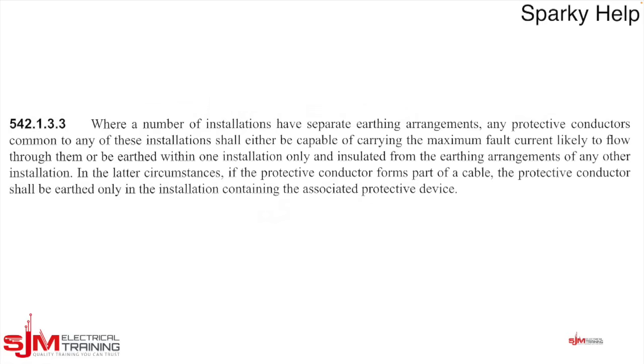So what do the regulations have to say? Well, they say where a number of installations have separate earthing arrangements, i.e. you go into an outbuilding, any protective conductor that is common to these shall be capable of carrying the maximum fault current. As you can see, the fault current path could flow through them. So the armoured cable that was going out, that now has to be sized the same size as your earthing conductor. So if that's a 16 mil, then the armouring has to be an equivalent to 16 mil as well, which, bear in mind, you might have only put a 4 mil or a 6 mil cable out there for your live conductors. You've now got to run a bigger cable or a separate earth to provide that fault current path. So that's one way you can get over it, and that's run a much bigger earth for the just in case moments.